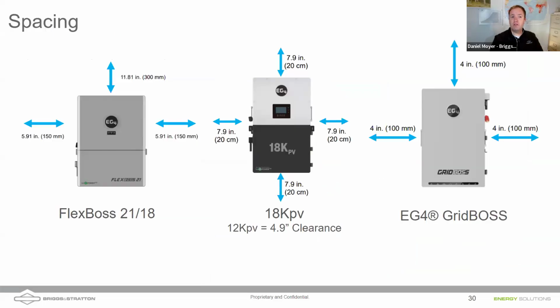Another reason I like EG4, specifically the FlexBoss, is that they're sealed. There is still fans, but the fans are just blowing across heat sinks that are external to the cabinet of the inverter. So there's no way for dust and dirt to get into one of those FlexBosses. Also, the way EG4 designed the FlexBoss is that it can fit flush up against a gutter, a wiring trough that's directly underneath the FlexBoss. That means you don't have to do the little stub conduit going down into a gutter. Really nice. I like that feature, although you still need to have some space on the sides and the top of the FlexBoss 21 and 18.